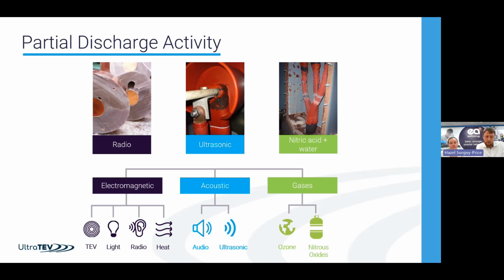All the bulk of the instruments we produce are designed to be used in the system live, so we're sitting on the outside of the box, outside of the switchgear, trying to identify this small spark that's going on. You can think of this spark in very much the way you would for an igniter on a gas oven, a piezo type igniter - a very fast, small release of energy.